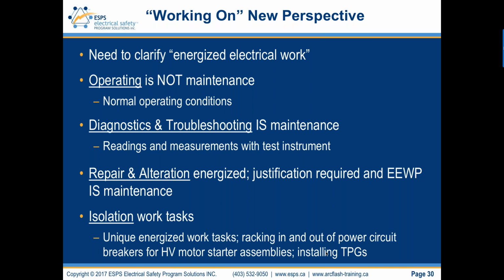The biggest item is operating. And right now there's this evolution in industry that normally operating energized electrical equipment has a high probability of an arcing fault, which is a false statement. It's not true. It hasn't been the case since we've created equipment that allows us to use electrical energy, and to operate the equipment that delivers it and gets it to the branch circuit equipment so that we can get some useful work from it. So we need to make sure that we don't go down this path. It has a significant impact, and we're setting a precedent that isn't correct. It isn't correct in the context of other equipment we use, specifically mechanical equipment that's operating in a normal operating condition. And we need to be very careful going down this path of operating energized electrical equipment and believing that it's an inherent arcing fault risk when it's not. So just again, a brief introduction of that new concept.